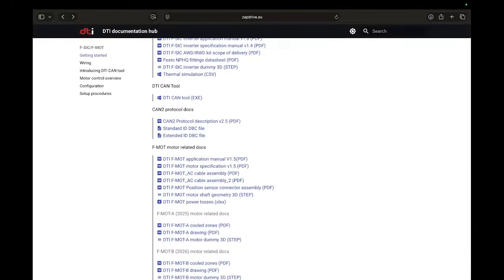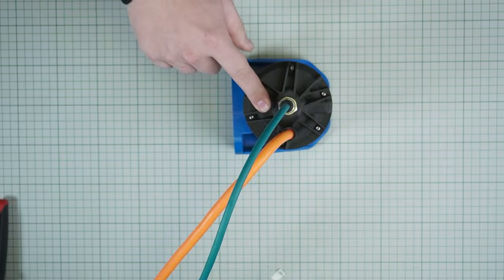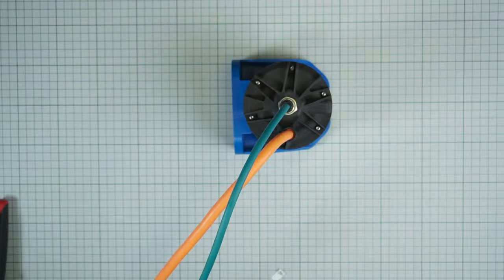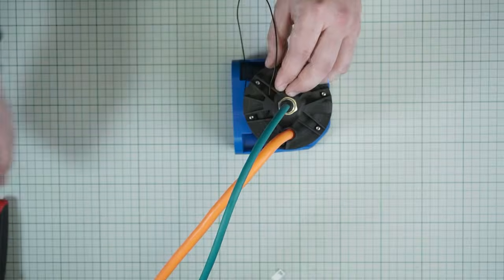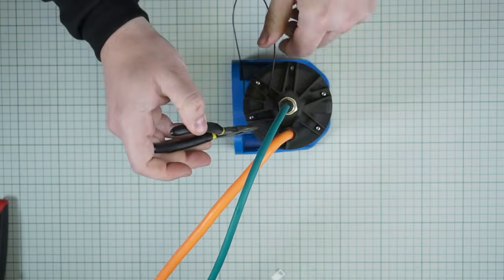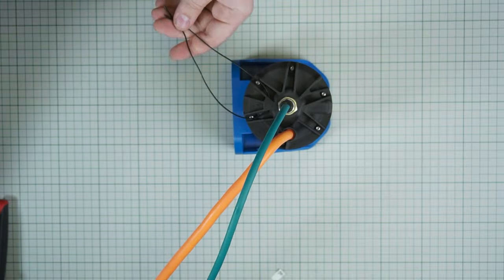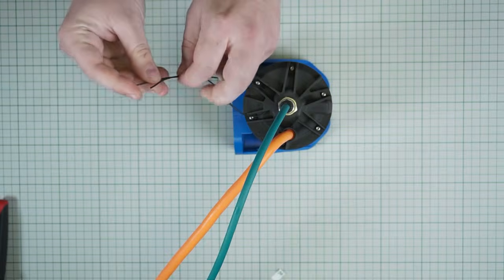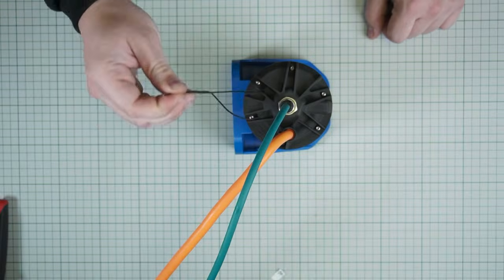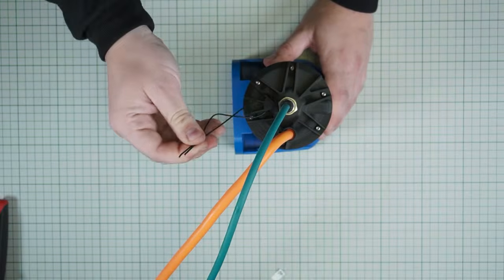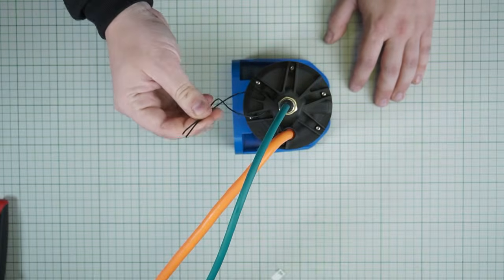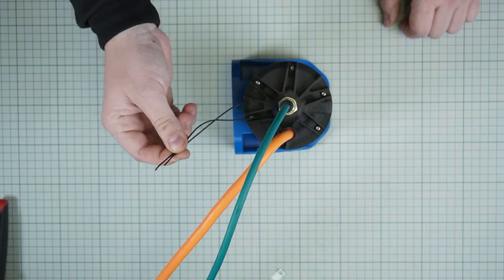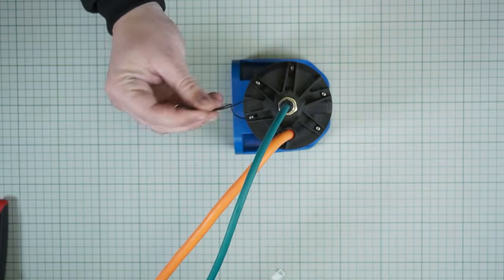Now with the motor showcased, I'd like to show you a bit more about the interlock wires. There is an interlock loop inside the motor. It's not a must to use this point for the interlock connection; it's just a loophole for the interlocks on the motor side. If you route this wire through the inverter and the motor's casing, you should be able to create a loop and make it this way. If you attach a wire-to-wire connector here, you can safely remove it from the system, so that's completely fine. Some teams have made it fully connected to the system, but we wouldn't recommend this, because then you cannot detach the cap from the system at some point. So we recommend using a wire-to-wire connection here.